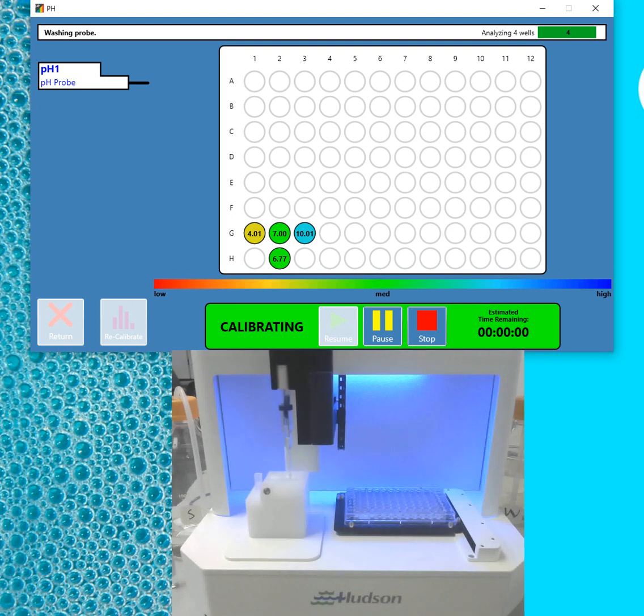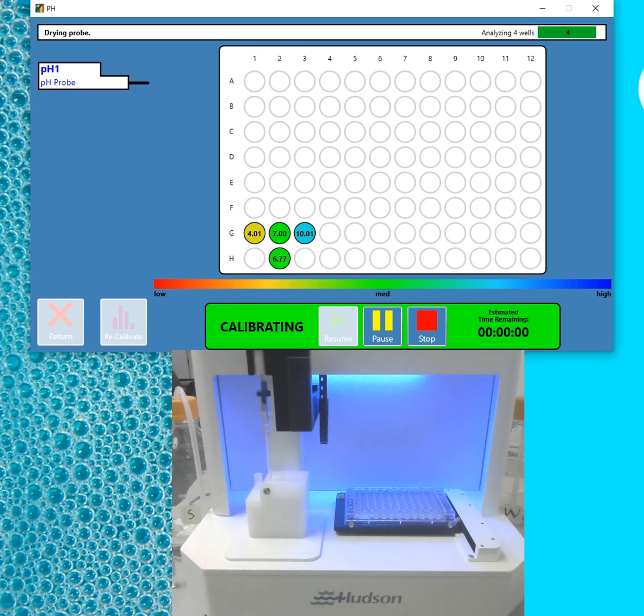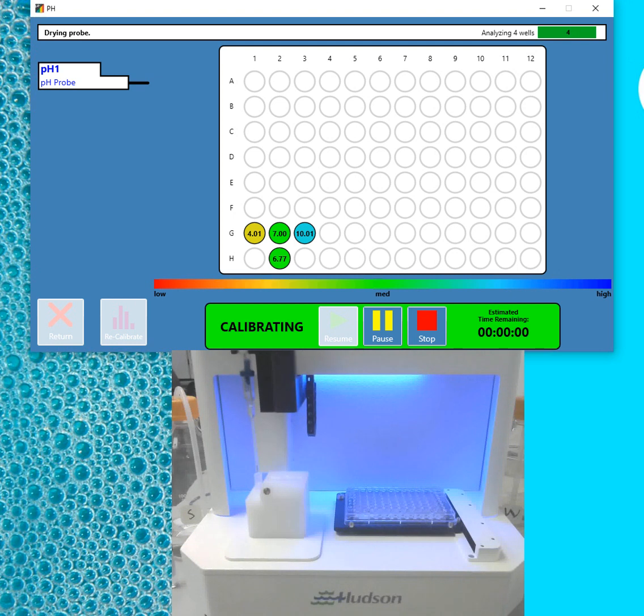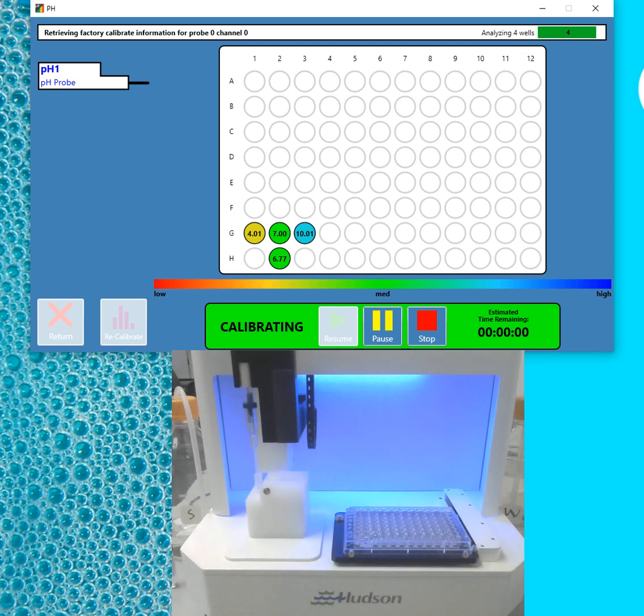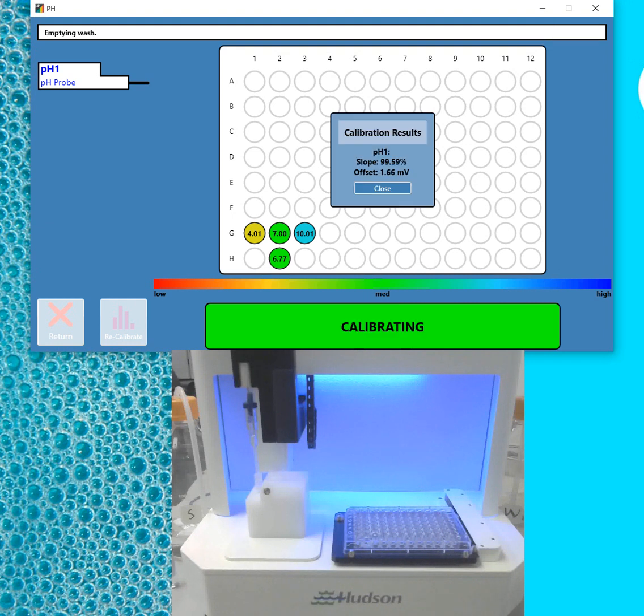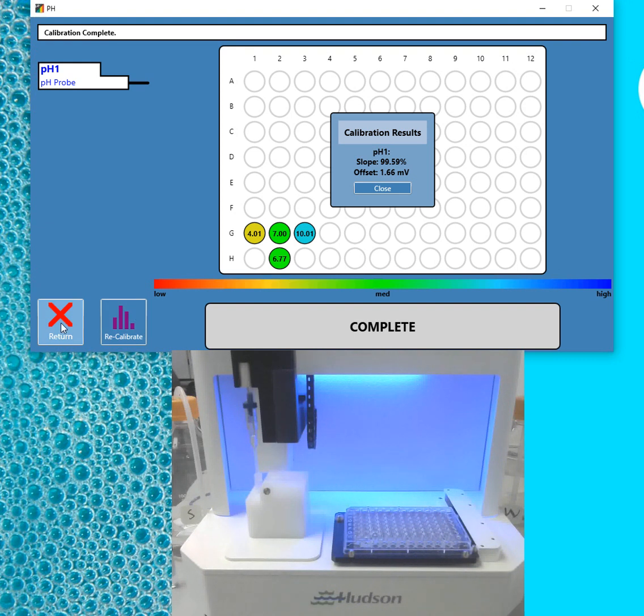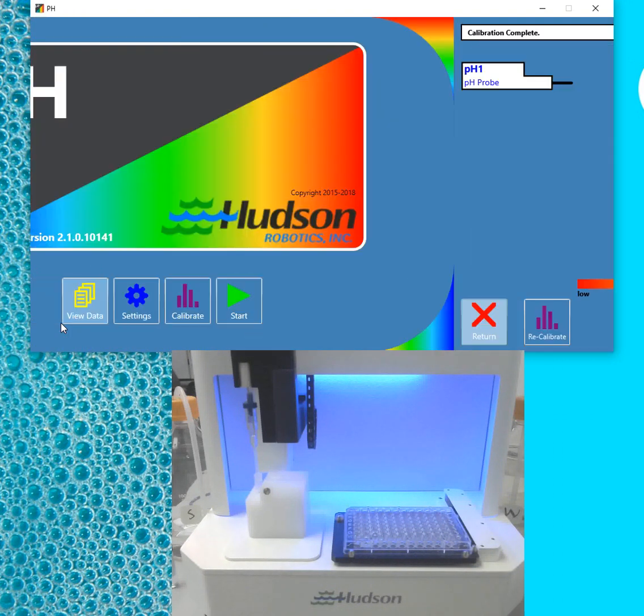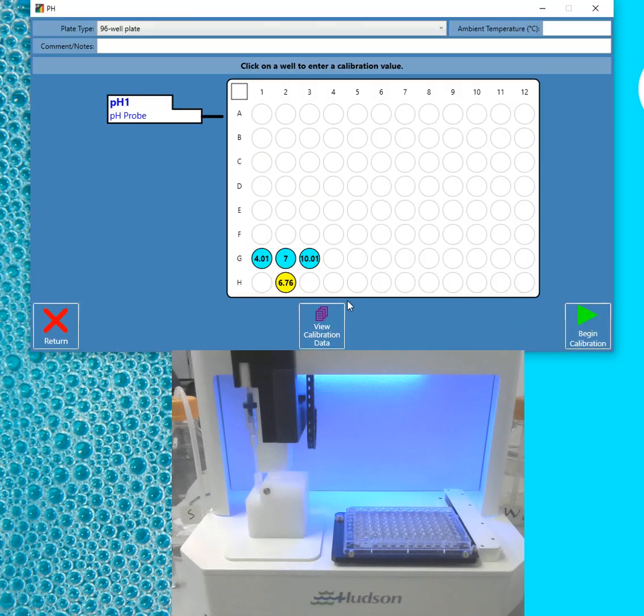So now we've run through all the samples, and we'll get the results. So if the results not within plus or minus 0.05, the calibration will fail. And now what I'll do is actually go out of the software, I'll go back into calibration, and show the view calibration data.